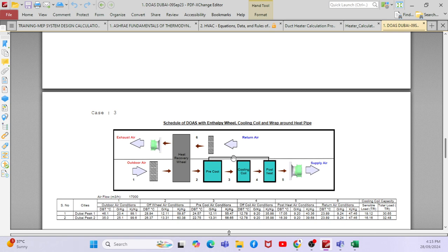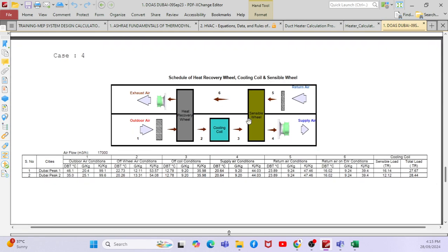See what is happening here. Assume this condition, when you talk about a fresh air handling unit, say the return temperature is 24 degrees Celsius. What is the temperature after the coil? Around 11 degree, 12 degree. So this energy will be transferred to the incoming supply temperature of 12 degree. When the heat is transferred, a heating process is happening, so the temperature will be increased. This is one of the points which you have to note.